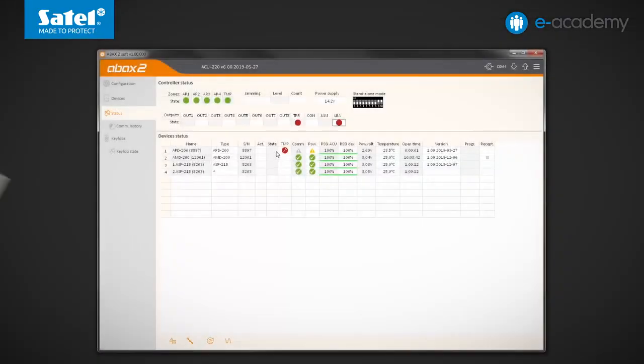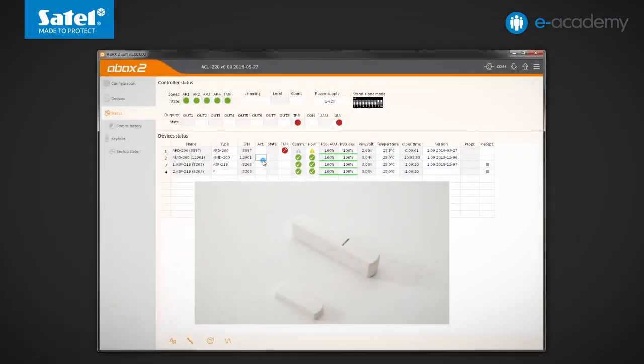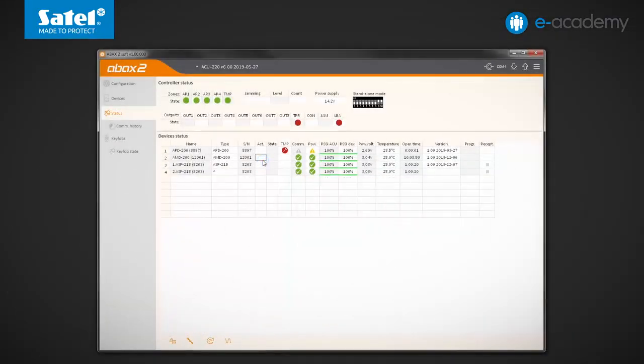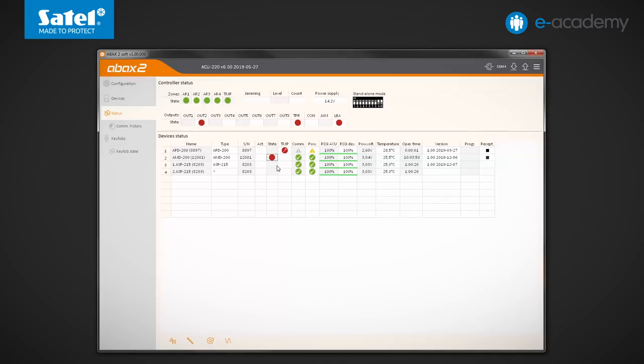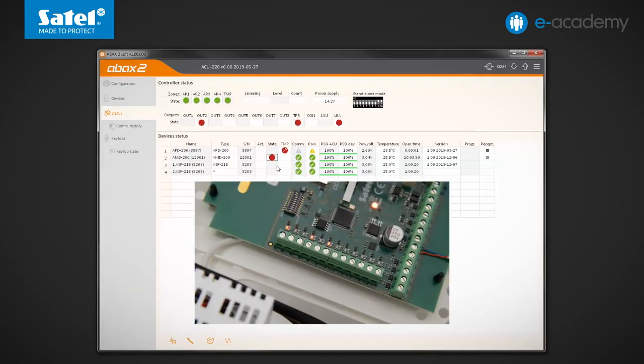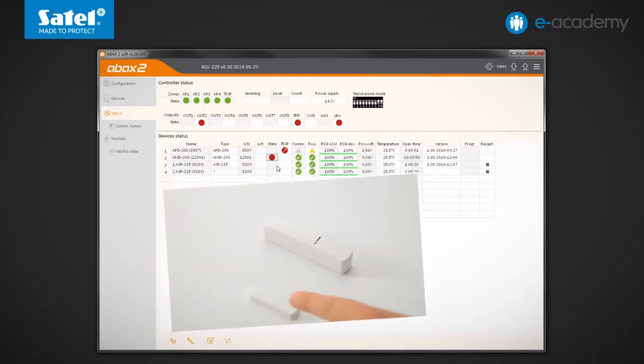Now we will violate the AMD200 by moving the magnet away from it. The detector is not in the active state, so information about its status will be sent only during the periodic communication. As you can see, the violation has been indicated in the program. This also activated the OUT2 output, which we previously associated with the magnetic contact.